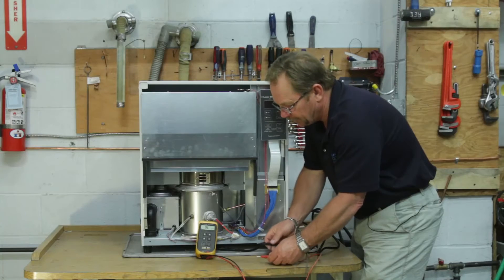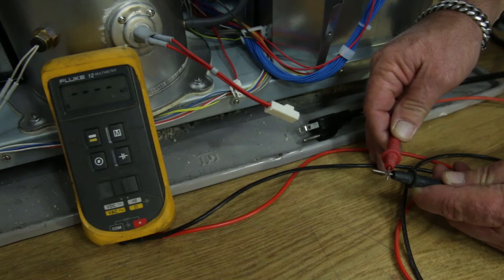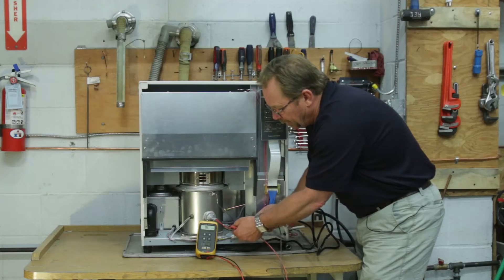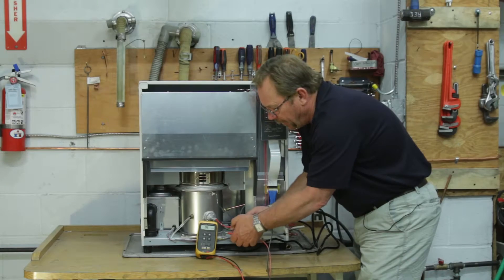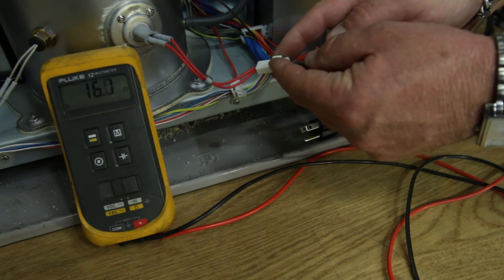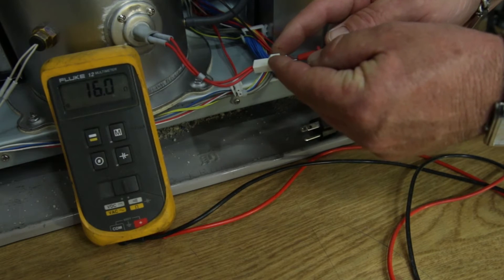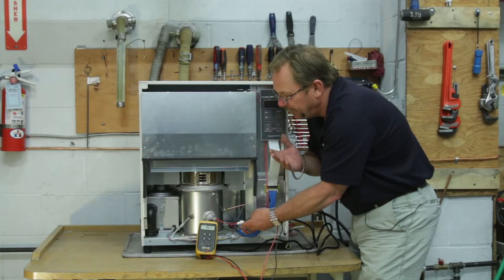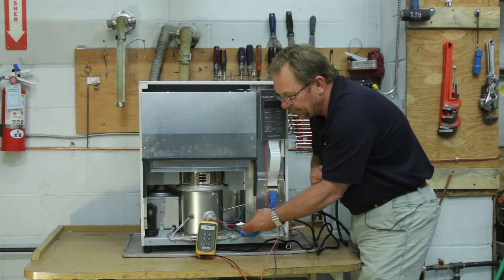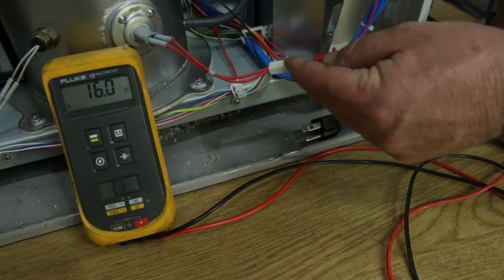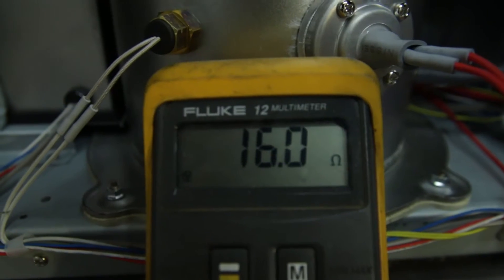Now we're going to touch our two leads together and we should get pretty close to 0.00, so we know that we're good. We come right in here and stick our probes gently in there, and we're getting our reading. Here we have 16 ohms of resistance, and we're looking between 16 and 18 ohms of resistance at room temperature. So we know that this igniter is exactly at factory spec.